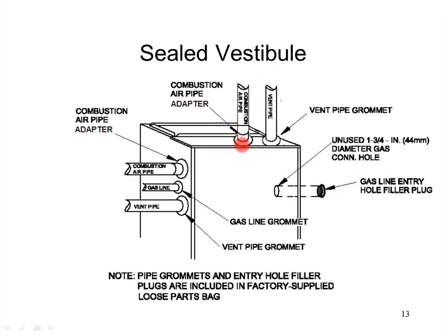Each one of these guys, each penetration, whether it's a vent pipe, combustion pipe, gas line, electrical connection, whatever, each one of them is going to ship with some kind of grommet to fully enclose that unit. So I don't want to put a gas pipe to the side of this cabinet and have an air gap between the gas pipe and the cabinet. There's a grommet that comes with that you'll install over the pipe to keep this guy reasonably sealed combustion. The top half of this furnace is a sealed combustion chamber. So if I punch holes in it to run pipes through it, I want to make sure those are sealed back up.